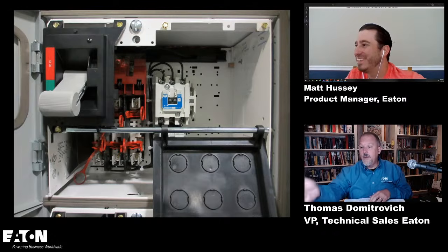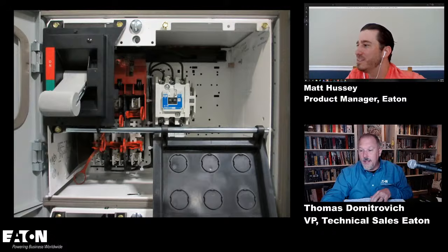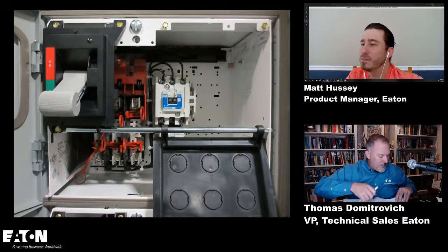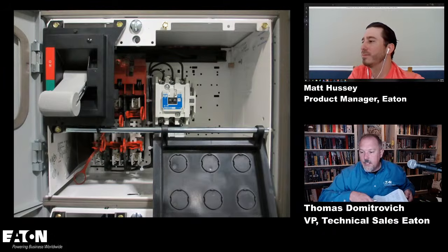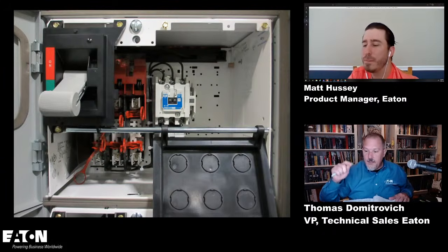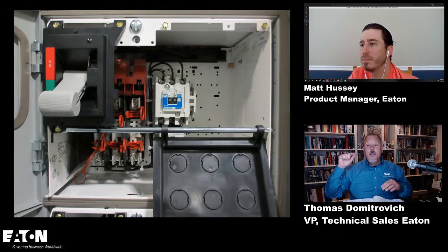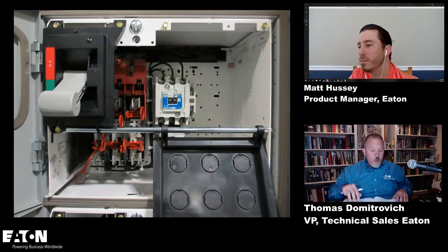There it is. So look at it. Ryan Jackson says nothing, I love it. Nothing that he knows of requires a listed MCC. I think the AHJ can use 110. I knew it was 110.3(A) to determine suitability if it was altered. So that's true, 110.3(A) does give them the ability to do that.